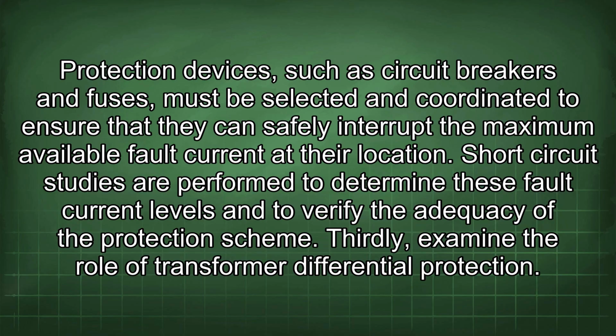Protection devices, such as circuit breakers and fuses, must be selected and coordinated to ensure that they can safely interrupt the maximum available fault current at their location. Short circuit studies are performed to determine these fault current levels and to verify the adequacy of the protection scheme.